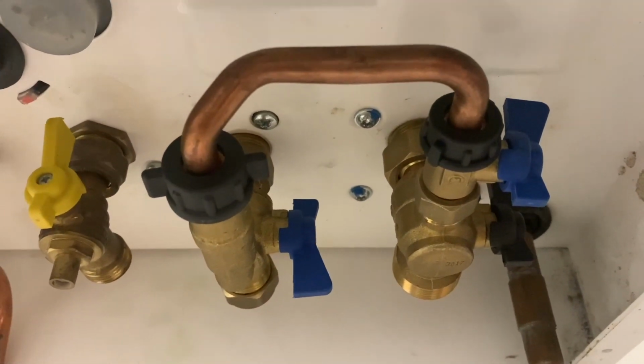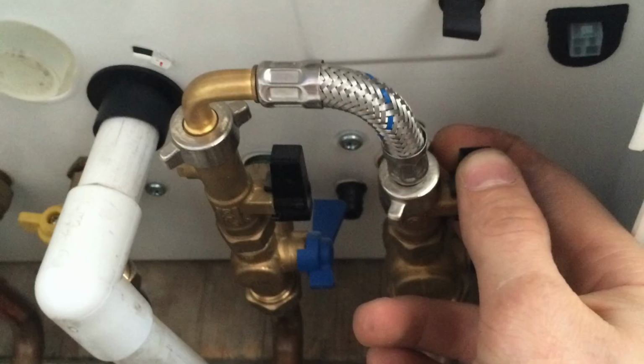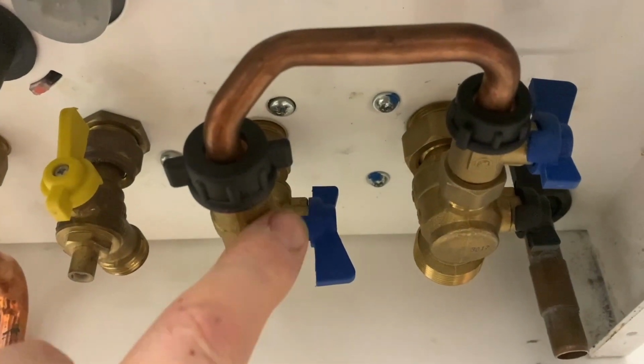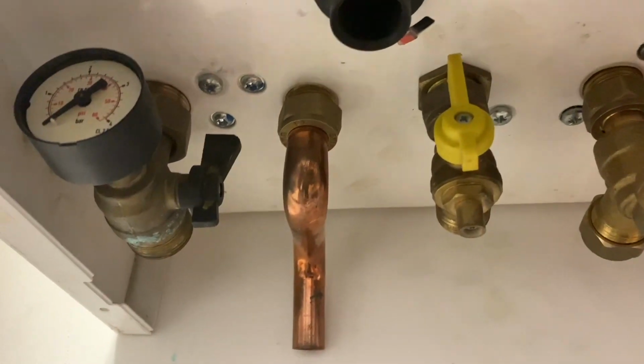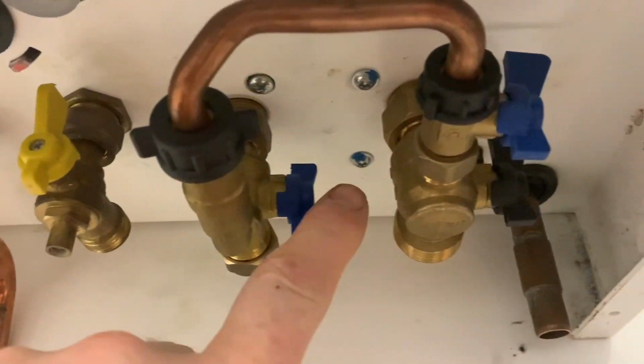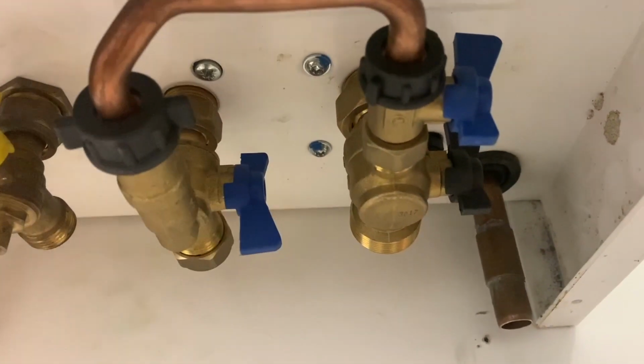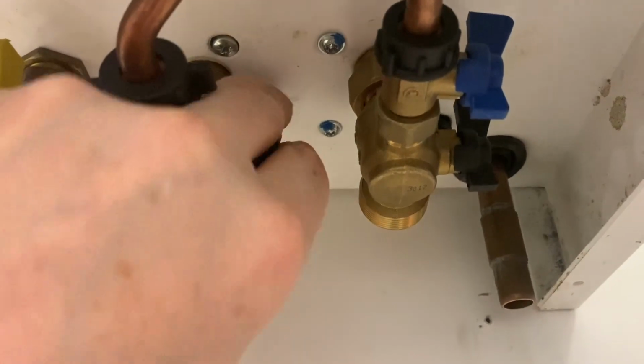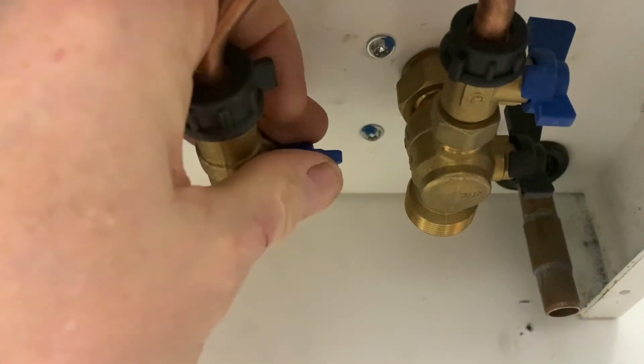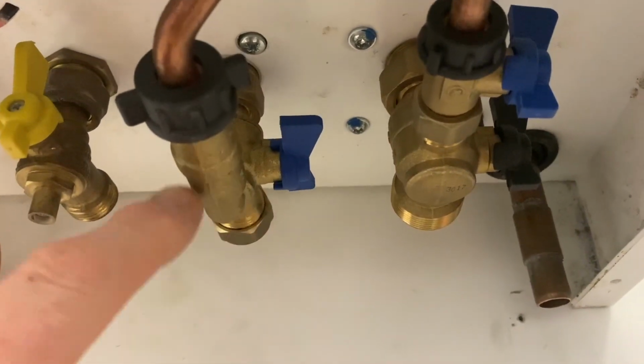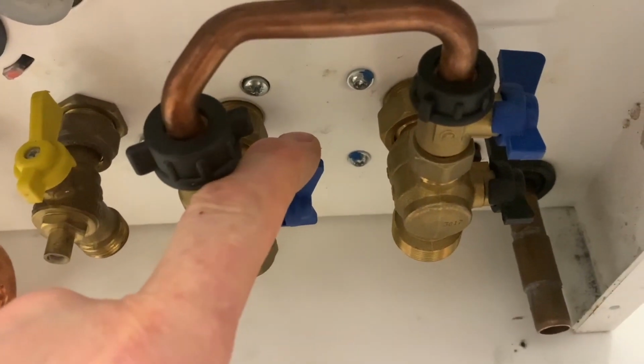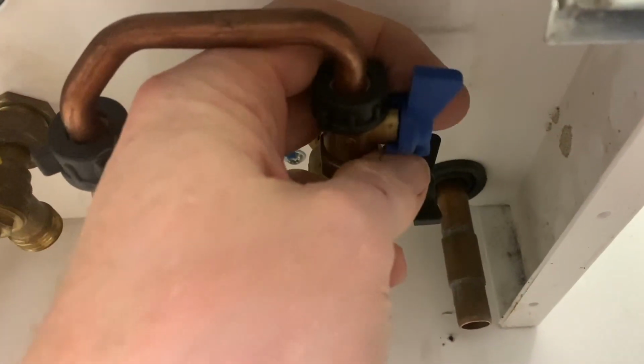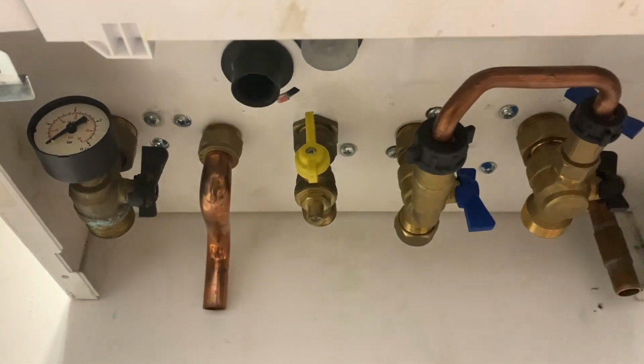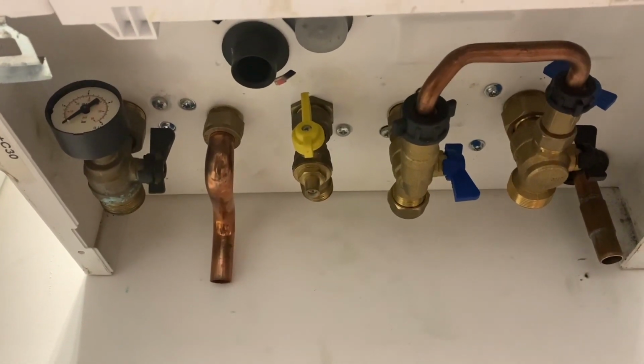Now, this is actually a replaced filling loop on this boiler. Originally, this would have been different. This would have had a silver filling loop, and there would have been another valve on here. The other thing with these valves is as well, is when they're up like that, it means they're on. And when they're in the horizontal, if I can put them on the horizontal, they all seem pretty stiff. Got there in the end. That's off. So, well, it's actually sending it through to the filling loop. So you have to watch out for that. So that one's on though and that one's off. So anyway, they're slightly different. So it kind of catches you out.